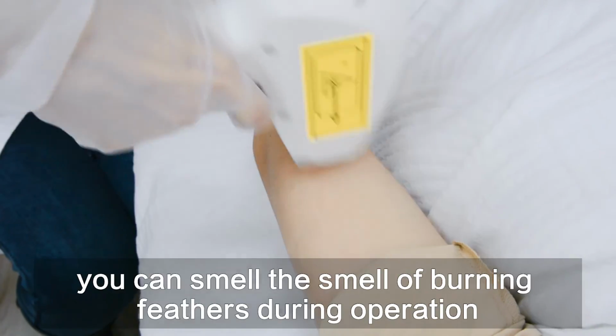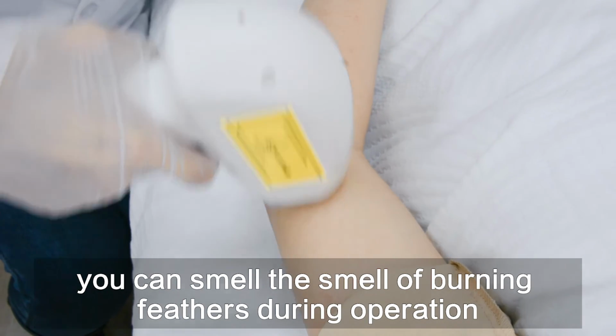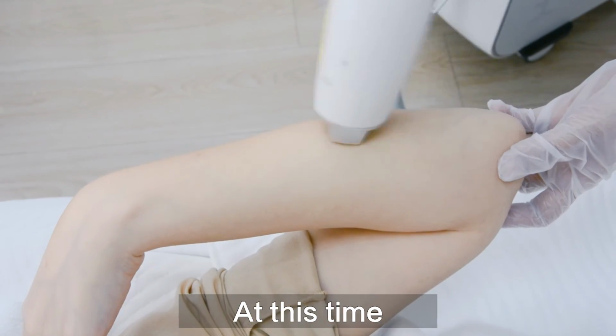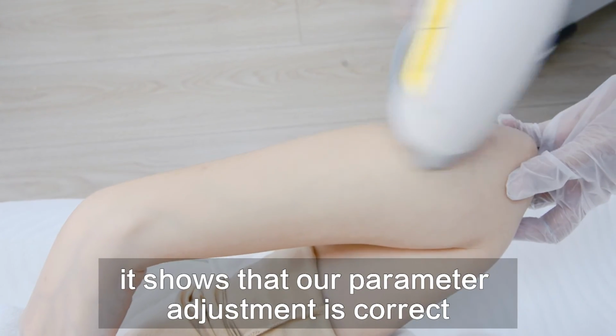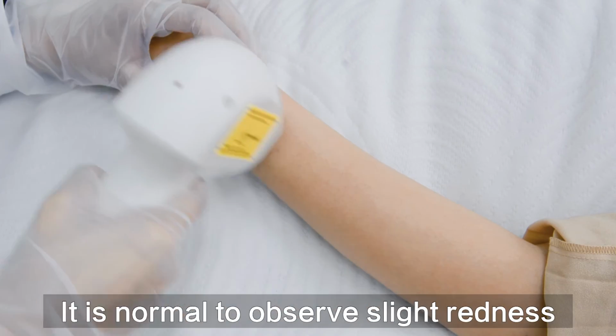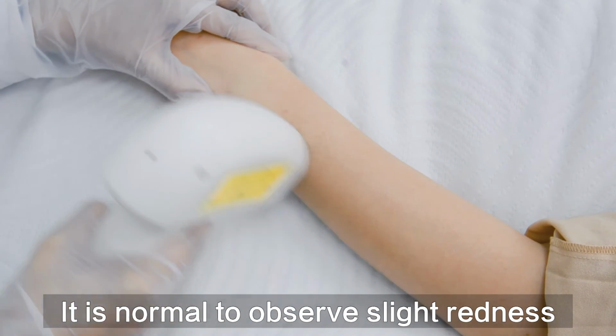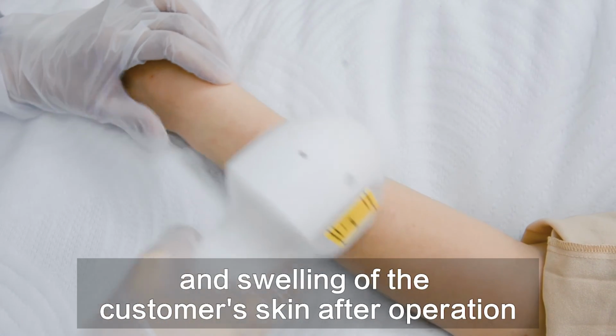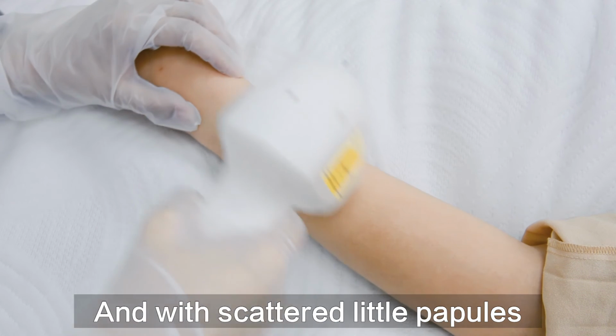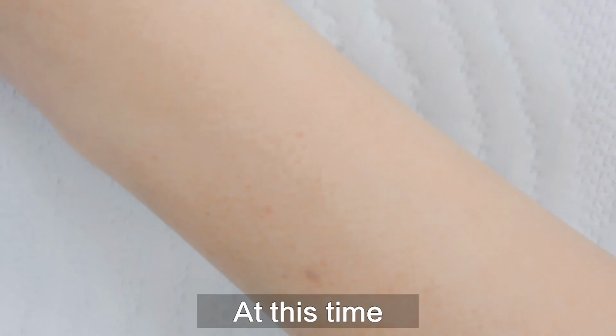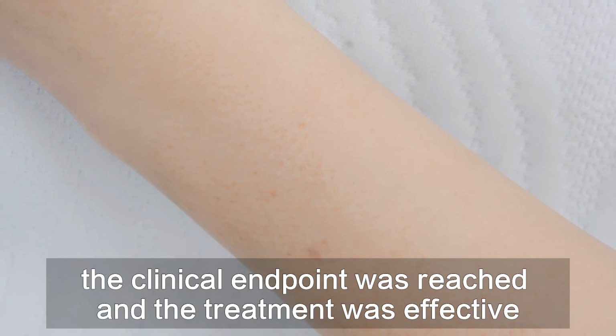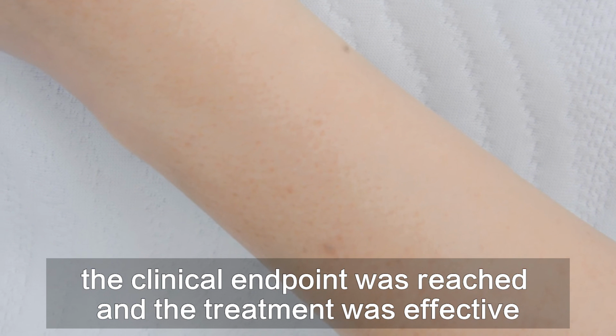In addition, you can smell a burning-feather smell during operation. At this time, it shows that our parameter adjustment is correct. It is normal to observe slight redness and swelling of the customer's skin after operation, with scattered little papules. At this time, the clinical endpoint has been reached and the treatment was effective.